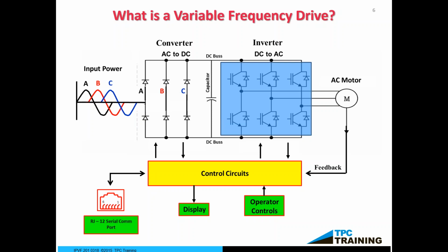If you had an oscilloscope, and we do have an oscilloscope, we would be able to see that traditional sinusoidal waveform on the primary side, on the left-hand side, converted to DC. It's really important to know that it's AC to DC. It's very predictable, that DC bus voltage. And if you could, make a note in your notepad there that the DC bus voltage will be much higher than the AC bus voltage. For example, and this helps when you're troubleshooting. This is very, very important. We'll get to the display and the control circuits there in just a second.